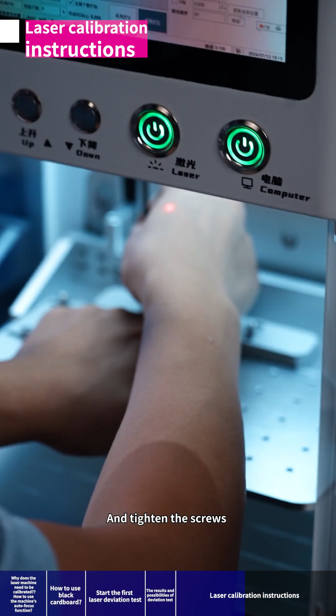Same method. After fixing it, let's check again whether the edge has moved. If no deviation, let's take out the cardboard. Now, we should change to another cardboard, because the one before has been damaged and it doesn't look good. Use another black cardboard that doesn't have wrong traces. Then put it on. As the screw has not been tightened yet, let's gently align it to the upper left corner.